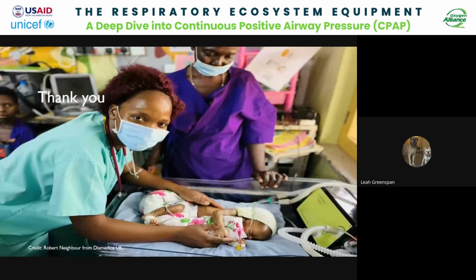And just to circle back on one point, if you're using a variable flow device, then the flow does directly impact the PEEP. Those were the two differences between the continuous flow and the variable flow. With continuous flow, like bubble CPAP, the flow does not affect the PEEP, whereas with variable flow it does. So in the variable, you dial your flow to maintain a PEEP of around 5 to 8. I hope that answers your question. Yes, it does. Thank you.